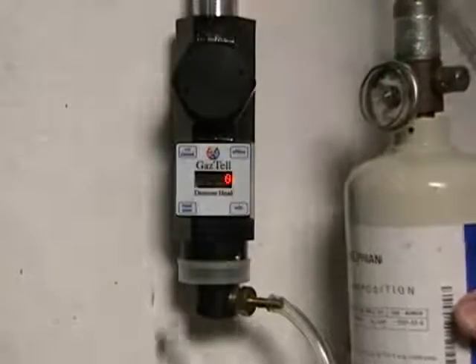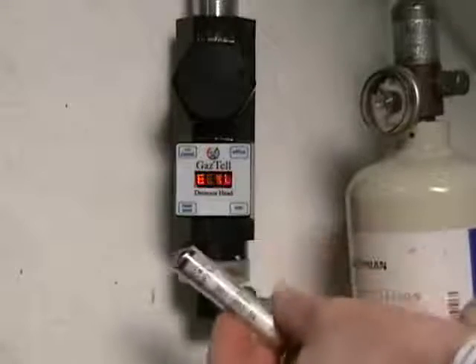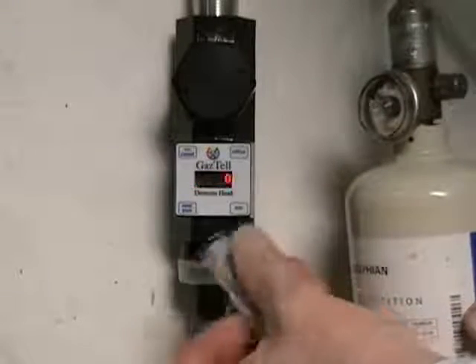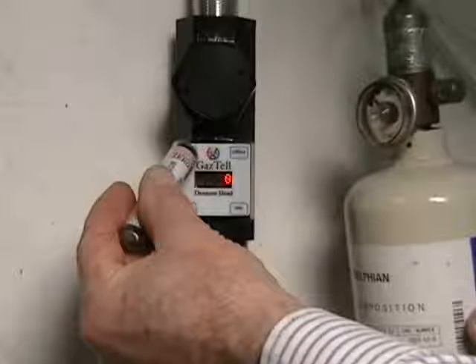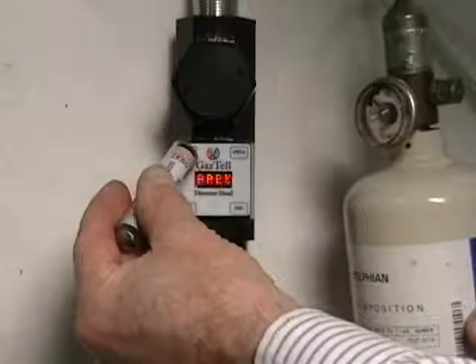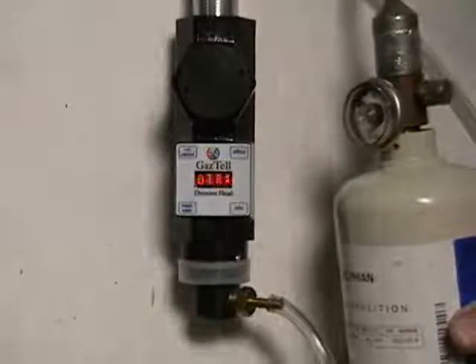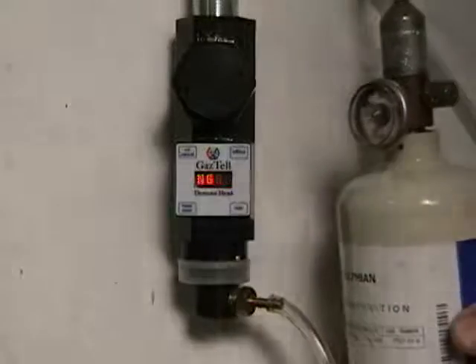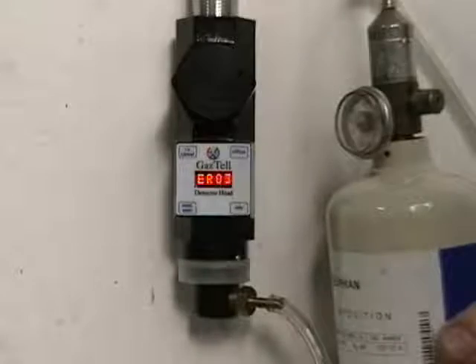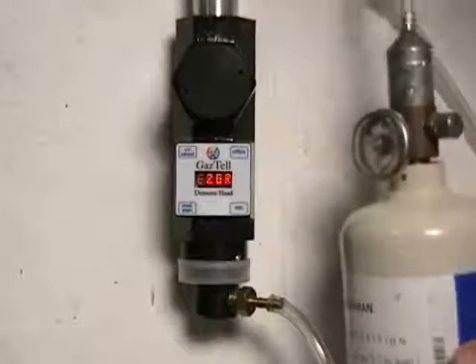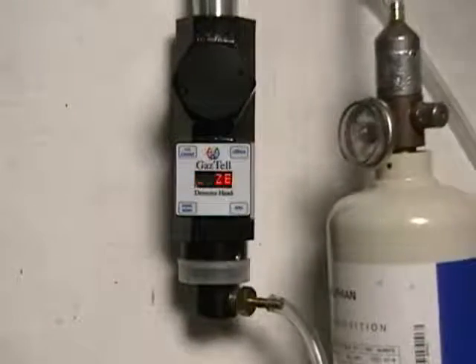Using the magnetic calibrator, start the zero calibration sequence by holding the red end of the calibrator over the cal mark on the label for 5 seconds. Apply zero air will be displayed. If you haven't already, turn on the zero gas regulator valve. The display will inform you when the gas flowing has removed the humidity from the sensor chamber to allow the zeroing to begin. The entire zeroing sequence typically takes about 30 to 40 seconds.